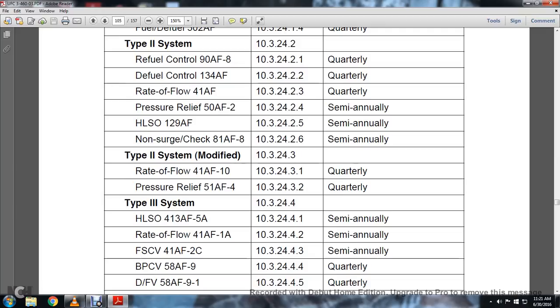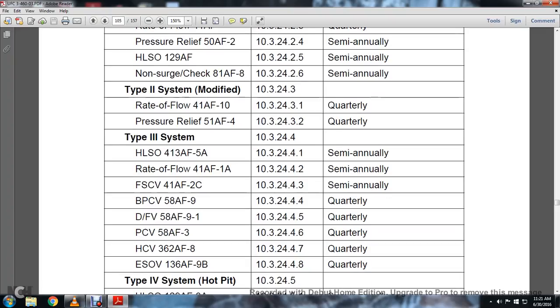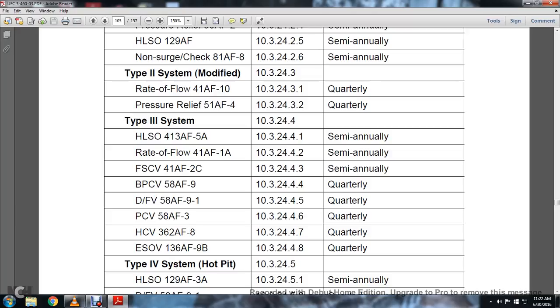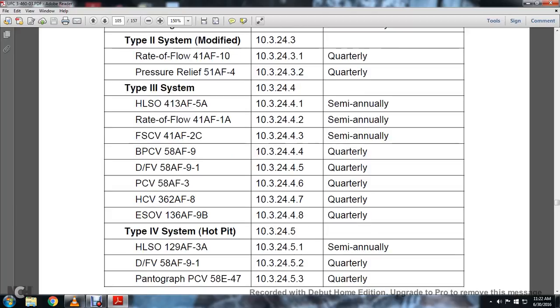Type 3 system. The high level safety operation automatic valve, 413AF-5A, 10.3.24.4.1, semi-annually. Rate of flow, 41 AF 1A automatic valve, 10.3.24.4.2, semi-annually. The filter separator control valve, 41 AF 2C, 10.3.24.4.3, semi-annually. The bypass control valve, 58 AF 9, 10.3.24.4.4, quarterly. The defueling flush valve, 58 AF 9-1, 10.3.24.4.5, quarterly. The pressure control valve, 58 AF 3, 10.3.24.4.6, quarterly. High control valve, 362AF-8, 10.3.24.4.7, quarterly. ESO valve, 136 AF 9B, 10.3.24.4.8, quarterly.